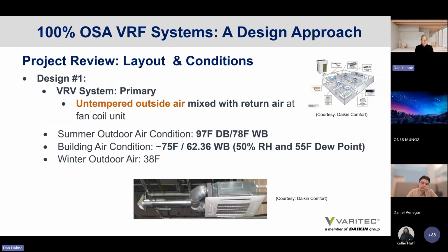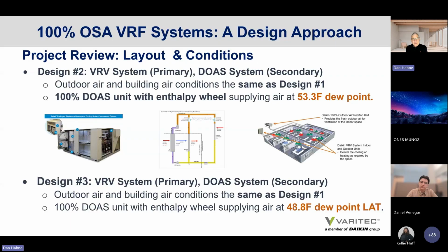And to support this concept, I wrote a paper in 2022 for Engineered Systems magazine on 100% outside air systems. We did an evaluation of 3 VRV systems with 3 different outside air conditions coming into the building. One was untempered outside air. One was design number 2, with a DOAS unit decoupled from the variable refrigerant system, with 55 degrees off the cooling coil or a 53.3 degree dew point. And then we looked at a low dew point DOAS solution that provided 52 degrees off the coil or a 48.8 degree dew point.